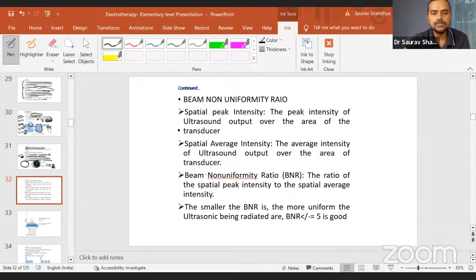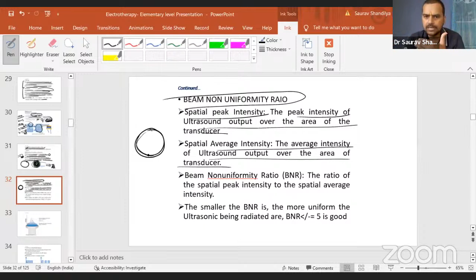One is the spatial peak intensity, the peak intensity of the ultrasound output over the area of the transducer. This is the area of the transducer where the spatial peak intensity is coming. Spatial average intensity is the average of the complete intensity coming out of this ultrasound head, an average of bigger, lesser, anything. So what is beam non-uniformity ratio? It is the ratio of the highest, spatial peak intensity, to the spatial average intensity.